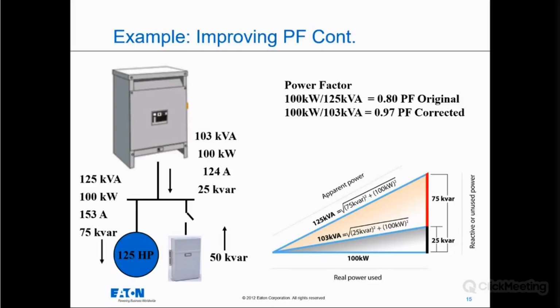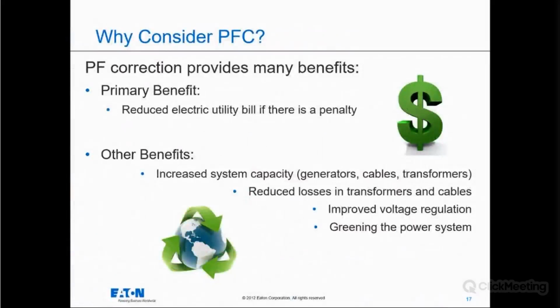So we're using our equipment more efficiently, not to mention that we would be able to add additional load onto this transformer because we now are operating at 103 kVA, freeing up some system capacity to add more load. If we look at our power factor, we see our original power factor was a 0.8, and now that we added this 50 kVAR capacitor, we now have corrected the power factor to a 0.97. A more efficient way to operate your system.